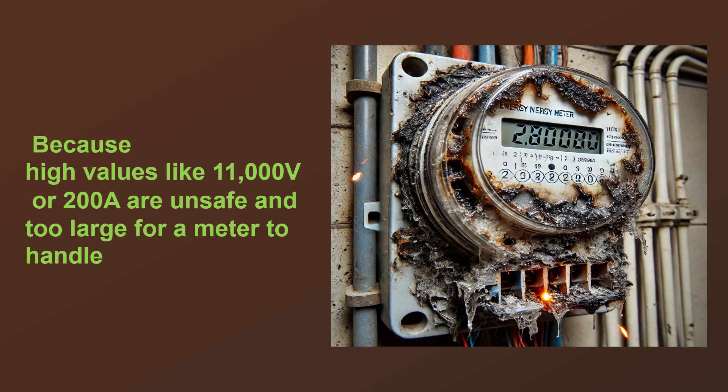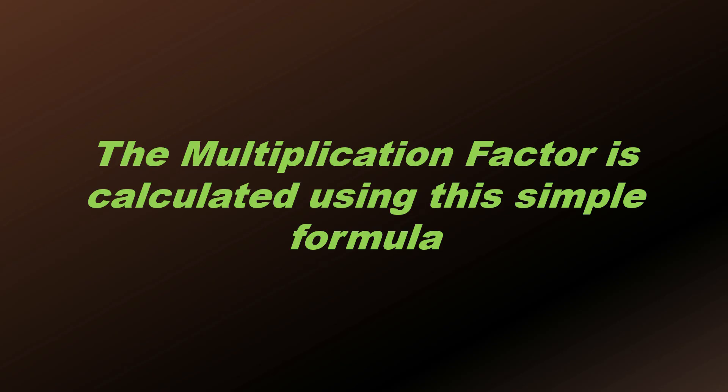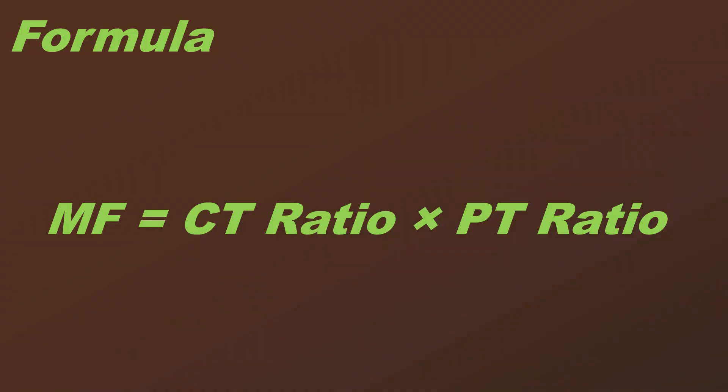The multiplication factor is calculated using this simple formula: MF = CT ratio × PT ratio.